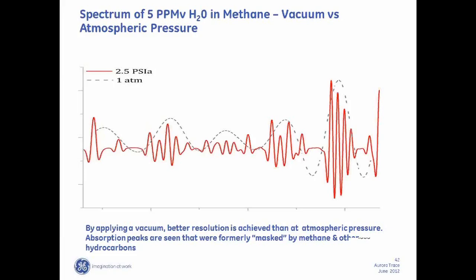And this is just another graph showing that at various concentrations. Now, there are 2 peaks in this one that we identify, and we actually use both peaks in the assessment of the water concentration. So again, we get a very sharp, narrow peak attributable to water, or actually 2 peaks, by operating this system under vacuum.